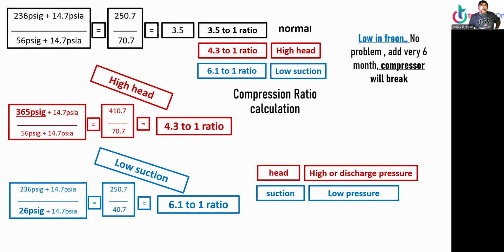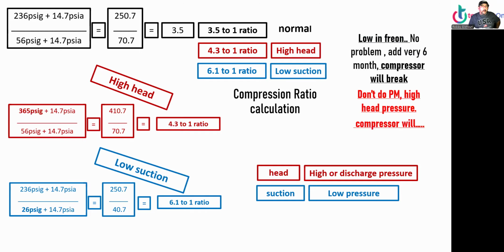Low on Freon, no problem. We add Freon every 6 months, the compressor will break. Don't do PM, no problem. Save money. High pressure, the compressor will break. Big problem. Alrighty, don't do PM, head pressure, compressor.